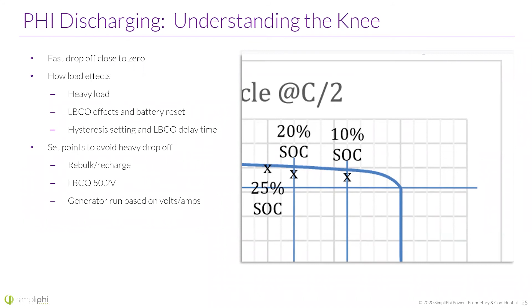But again, this knee doesn't typically come into effect for most residential systems, but I have seen a few industrial cases where they're using a really heavy, continuous load on the battery, and they note that their battery drops pretty fast, and they may need to take their low battery cutout delay and lower it so that the inverter goes into a state of disconnect before the battery has the ability to go into disconnect. Once the battery's gone into disconnect, it requires a manual reset. So it's not very fun, especially if the site's far.